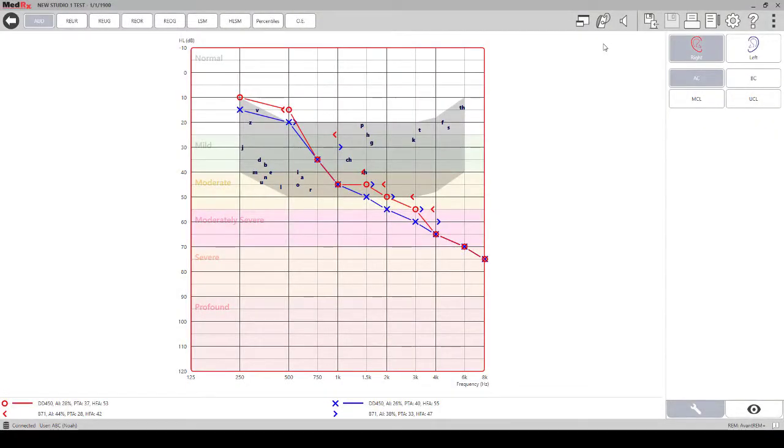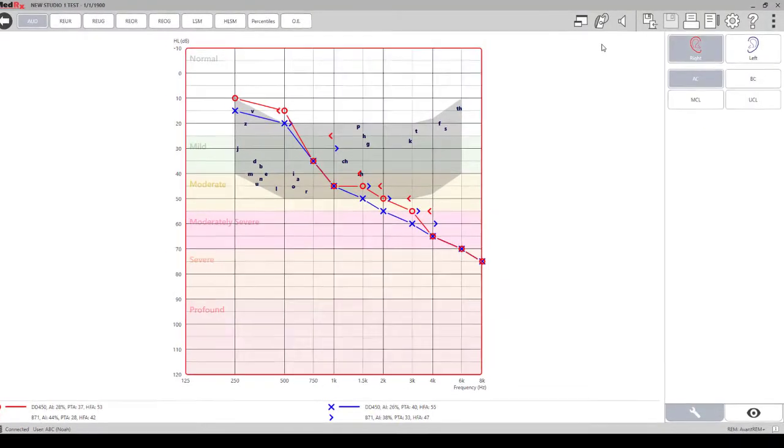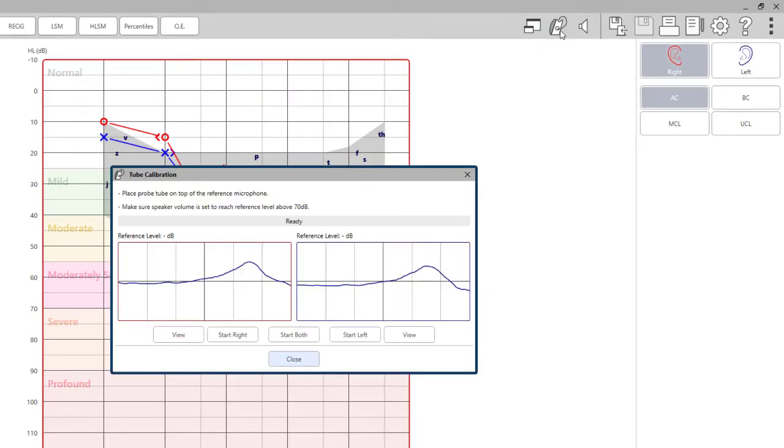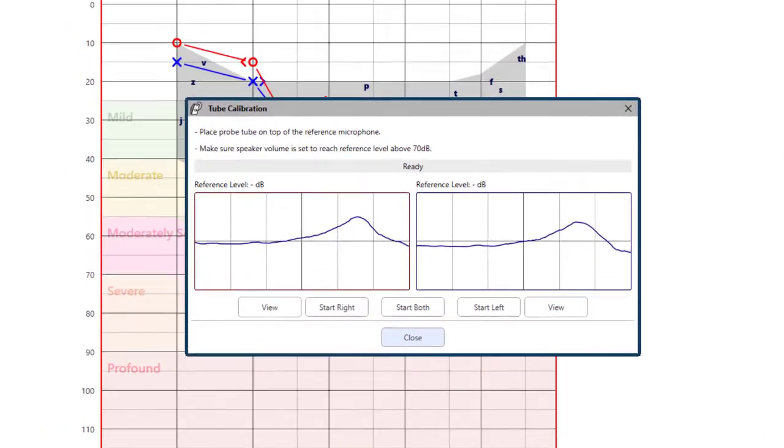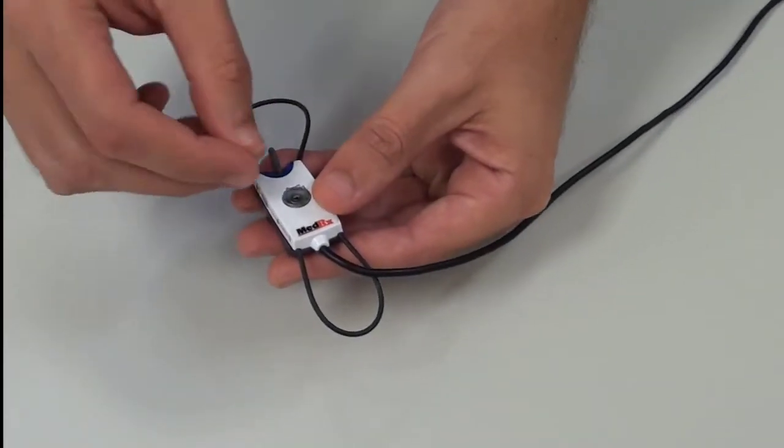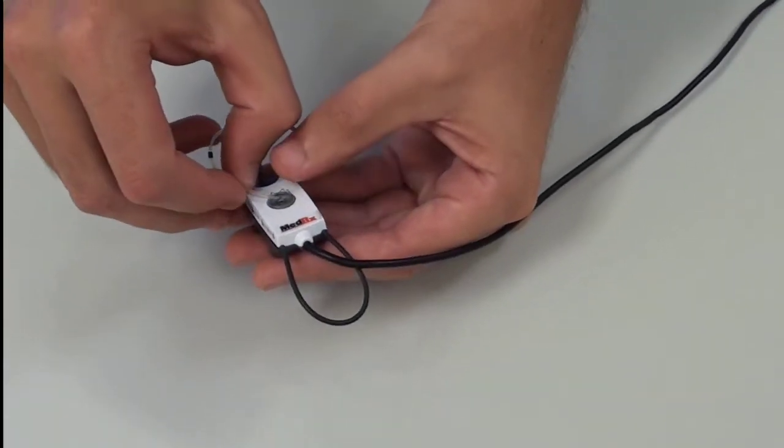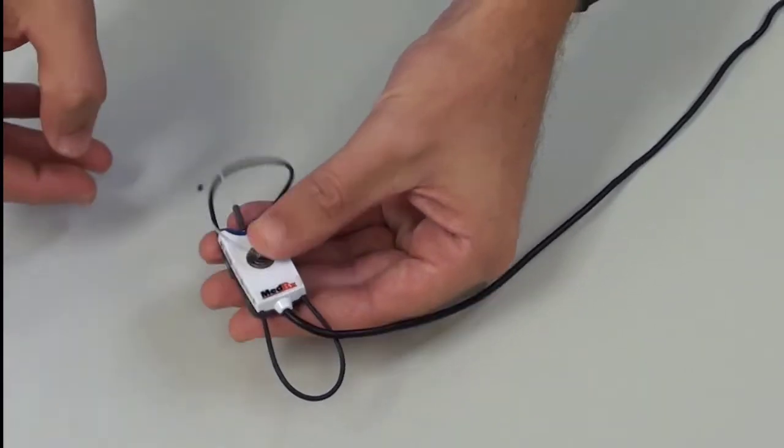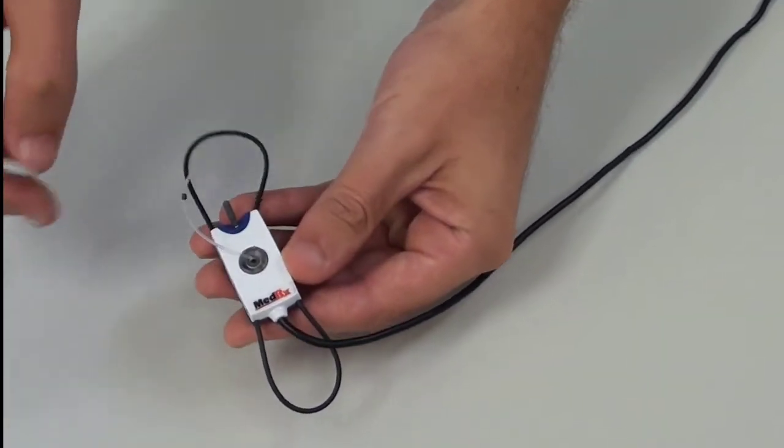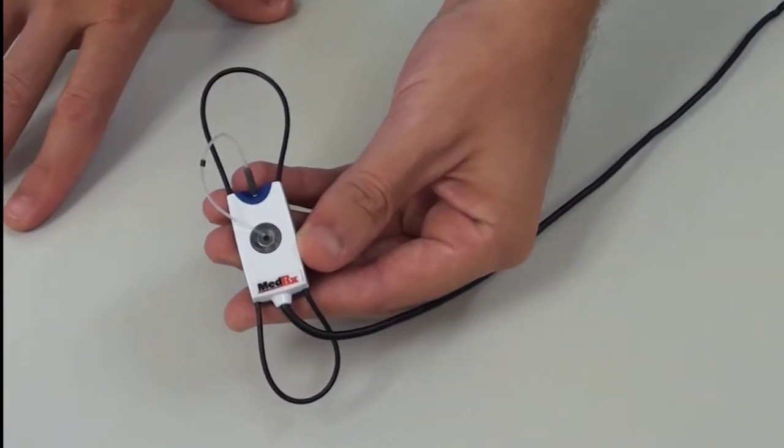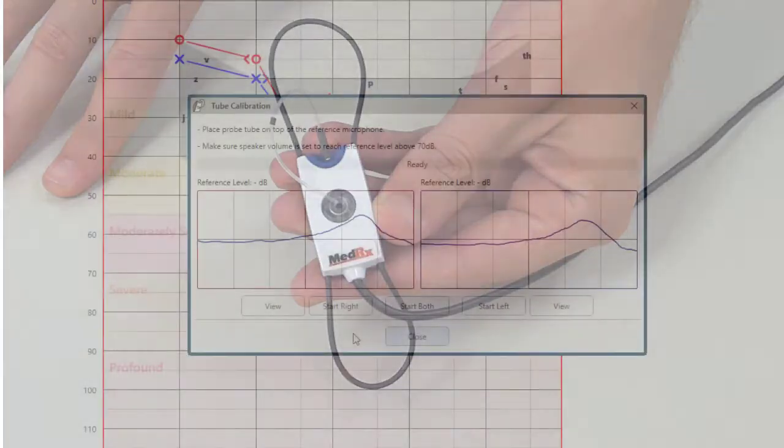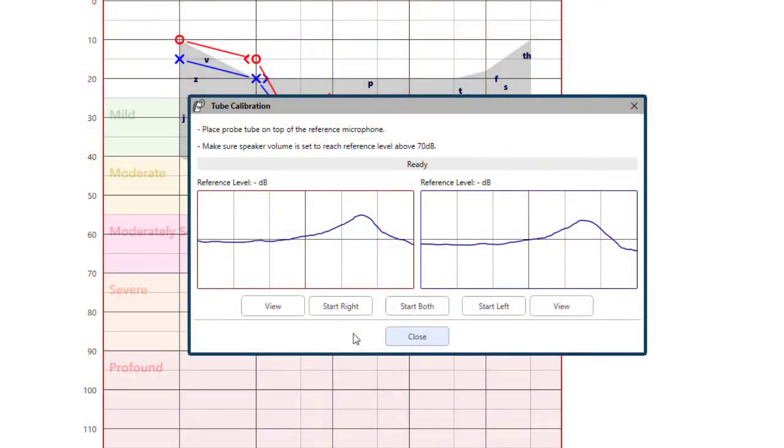To calibrate the probe tube, click on the probe tube calibration icon at the top of the screen. Place the probe tube between the calibration nibs on your reference microphone. Be sure that the opening of the probe tube is centered on the opening of the reference microphone. You can choose to calibrate the probe tubes individually or both at the same time. When you start the calibration you will hear the calibration noise from the speakers.